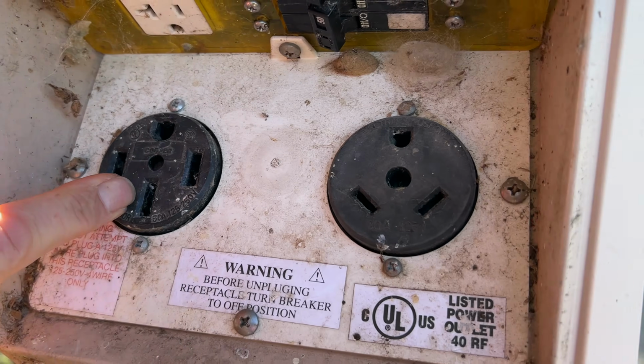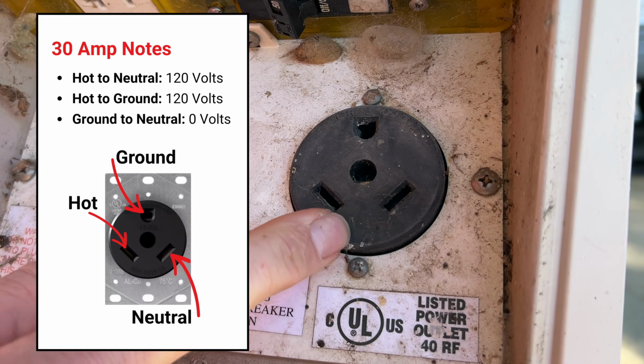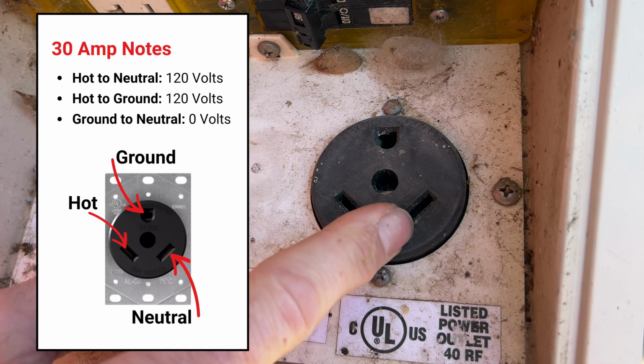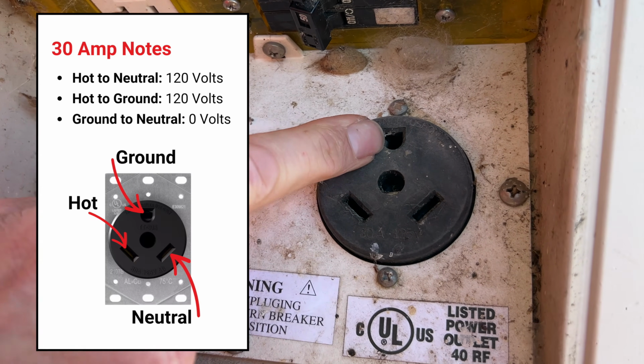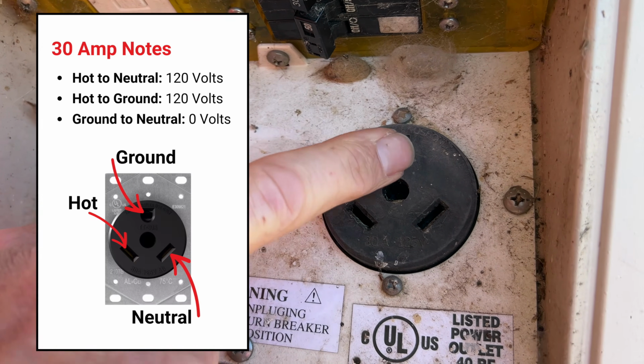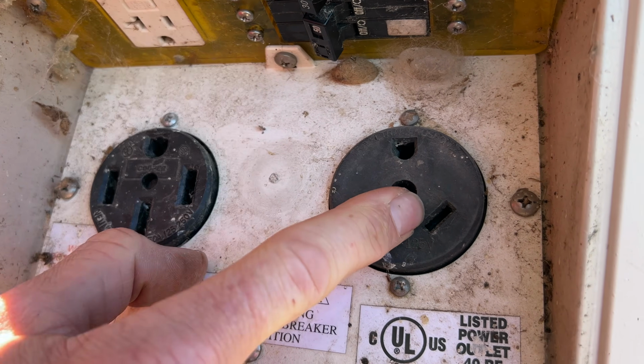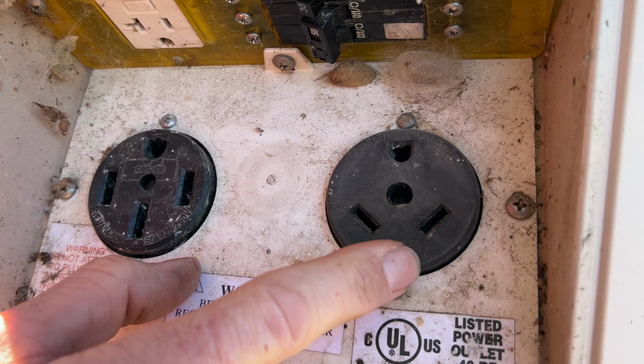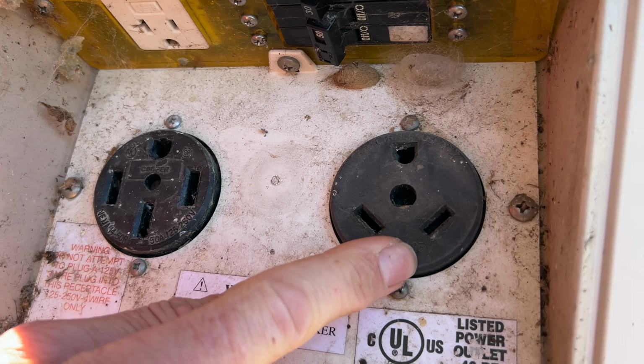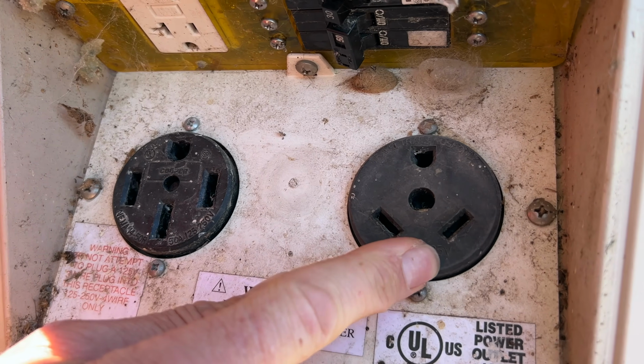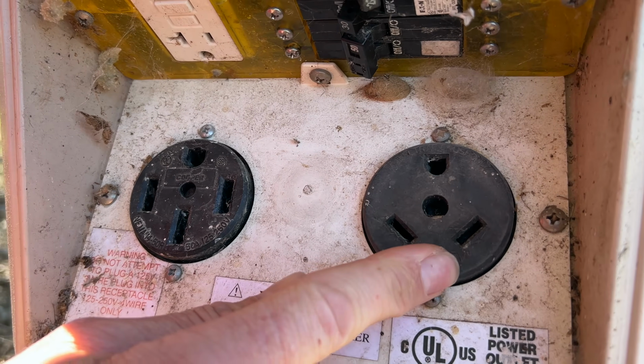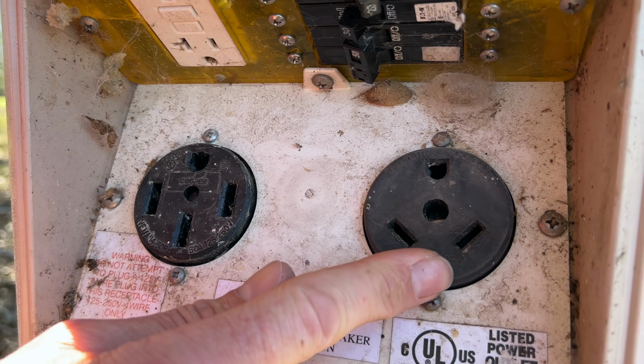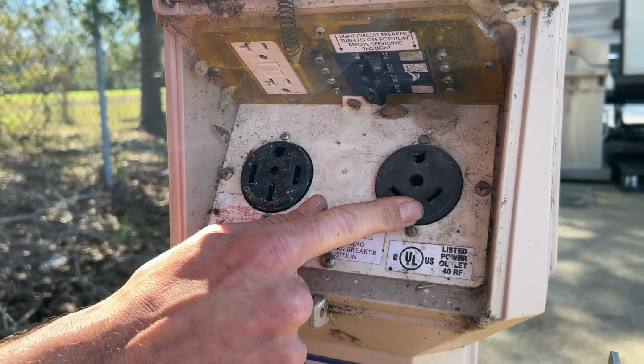That is all correct. Same thing on our 30 amp side. Between our hot to neutral was 120. Our hot to ground was 120. And our ground to neutral is 0. You do not want to see 240 volts on a 30 amp side. That will blow things out inside of your RV. That means the plug is not wired properly. It typically happens inside of people's garages when they plug in outlets.